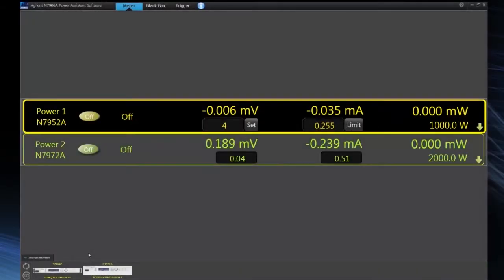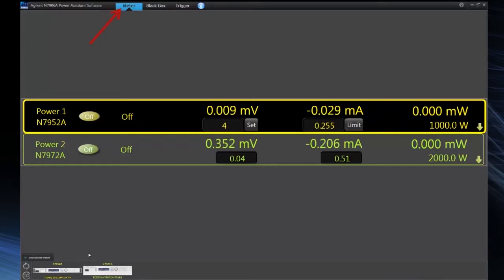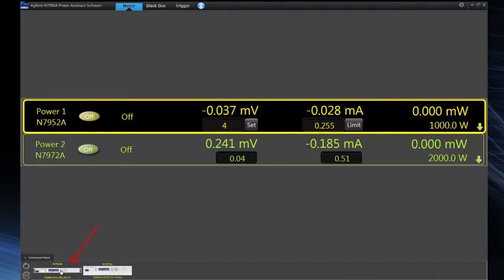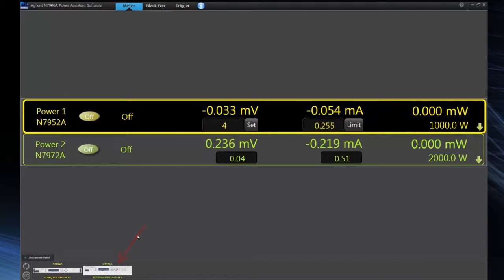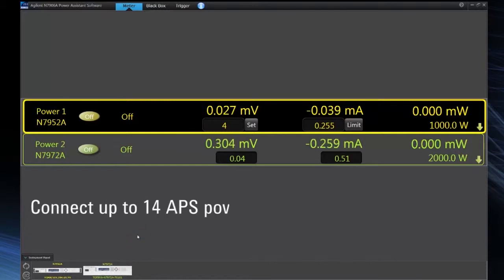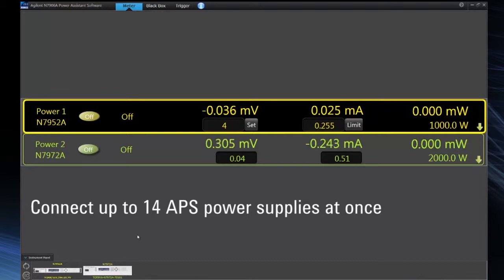So now we're looking at the Power Assistant software, the meter and control view, and right now we're connected to two Advanced Power System power supplies, a one kilowatt power supply and a two kilowatt power supply. We can actually use the Power Assistant software to connect up to fourteen Advanced Power System power supplies at once.